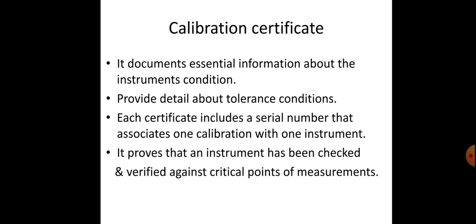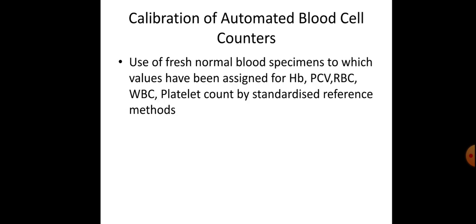Calibration certificate: it documents essential information about the instrument's condition. It provides details about tolerance conditions. Each certificate includes a serial number that associates one calibration with one instrument. It shows that an instrument has been checked and verified against critical points of measurement.